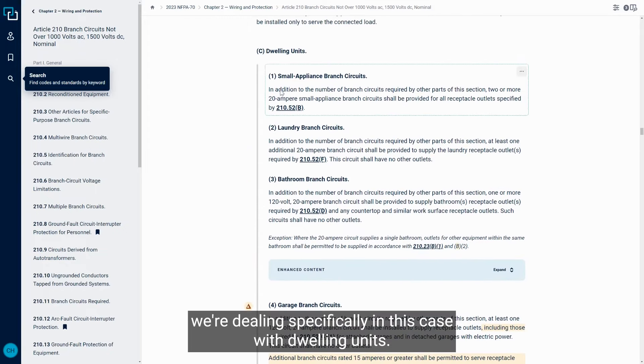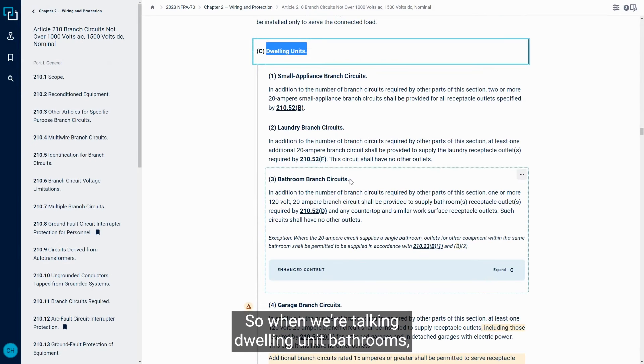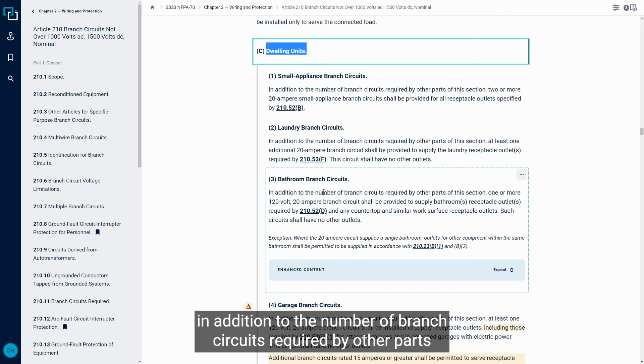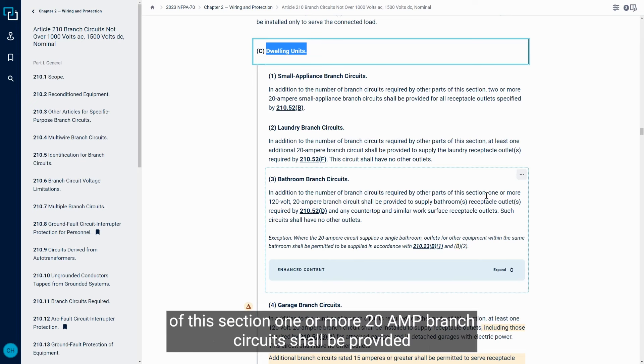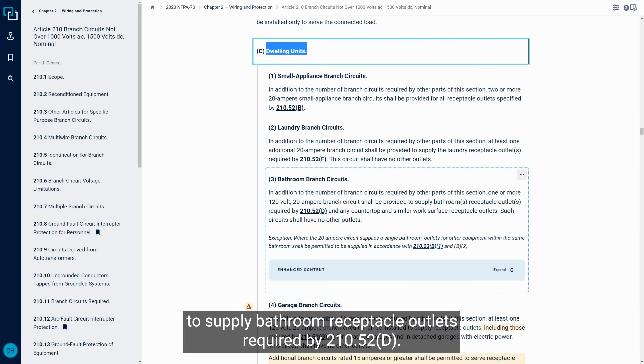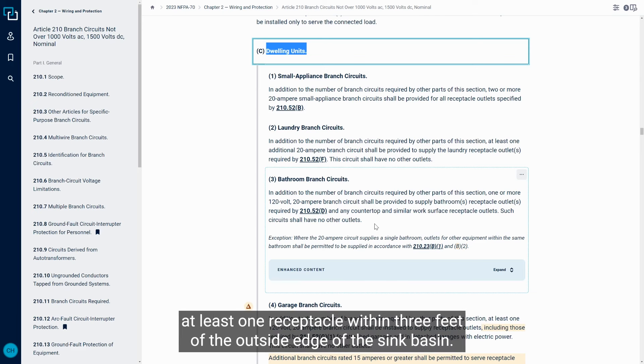And as we navigate over to that section, we're dealing specifically in this case with dwelling units. So when we're talking dwelling unit bathrooms, in addition to the number of branch circuits required by other parts of this section, one or more 20 amp branch circuits shall be provided to supply bathroom receptacle outlets required by 210.52.D. So we looked at that 210.52.D, that's where it said we had to have at least one receptacle within three feet of the outside edge of the sink basin.